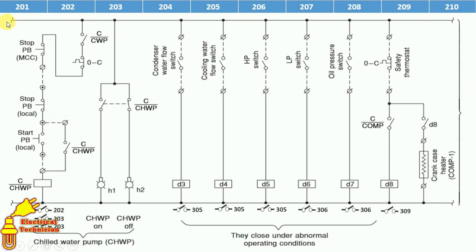Now this control supply which is going to next page. See, here supply is coming. From previous page, supply is coming here on this page. Now after condenser water pump, circuit is made for chilled water pump. This much circuit here, this is for chilled water pump. Now in chilled water pump also, same thing is done. First of all, one interlock is taken, that is from condenser water pump, interlock is taken. When this gets on, then only power supply will flow further.